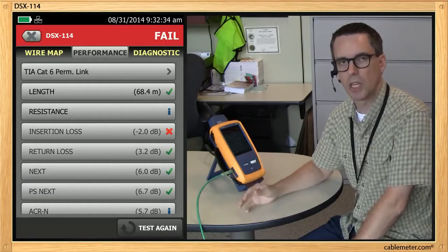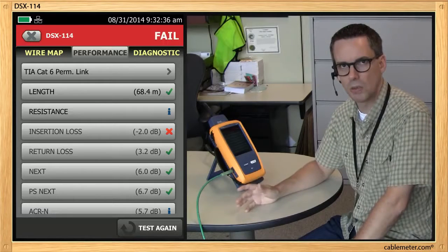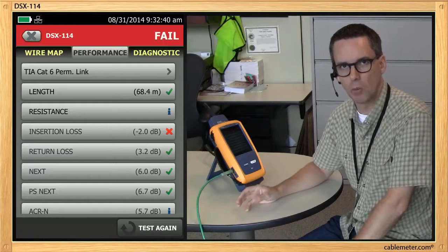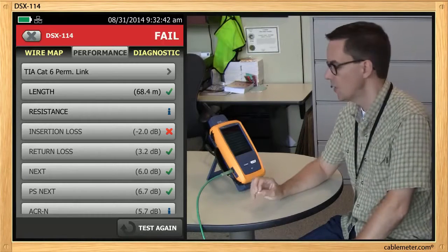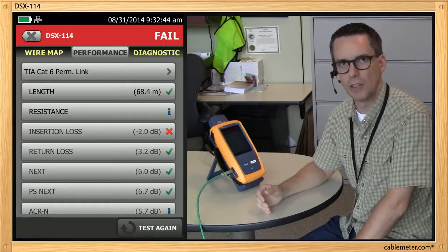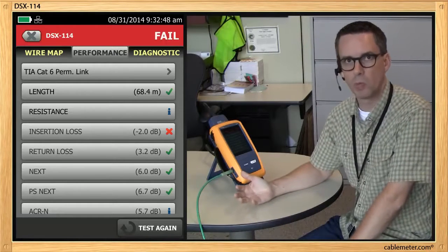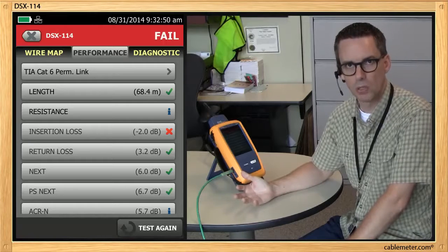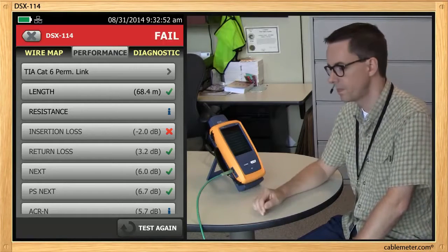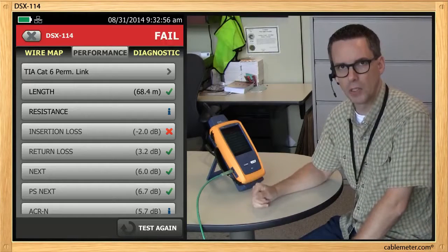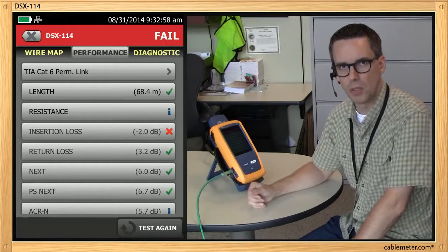If you are on a very tight time schedule, what you'll need to do is contact the lubricant manufacturers and see if they have an option for a lubricant that is not as conductive and doesn't cause such an insertion loss. And I'm not promoting any one company, but Polywater does do one. It's called FTTX. It comes in a spray or a wipe. And so if you're on that time-sensitive job, then that's something to consider.